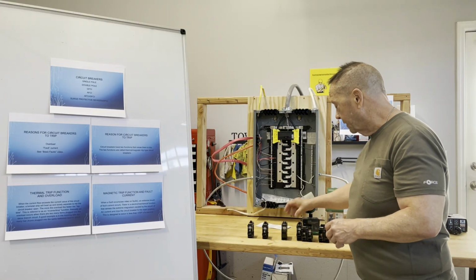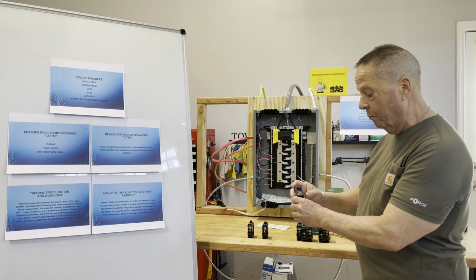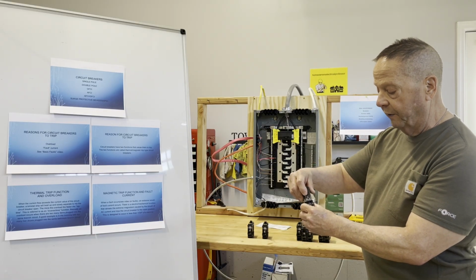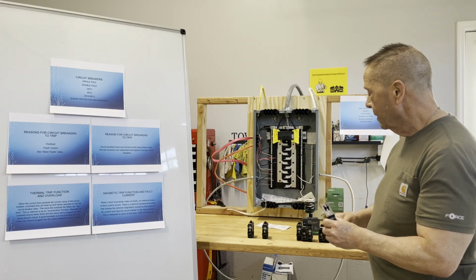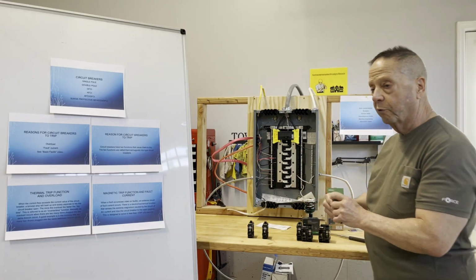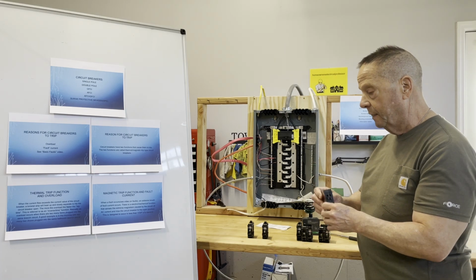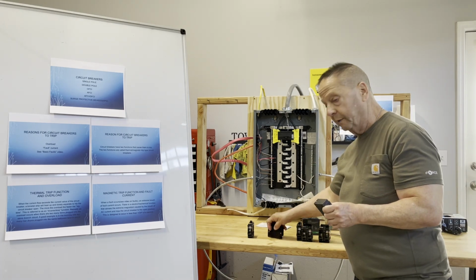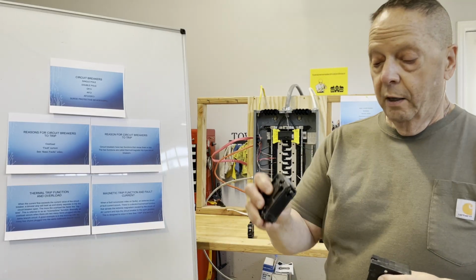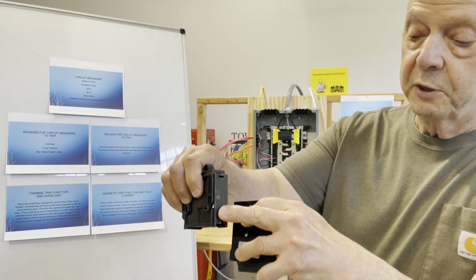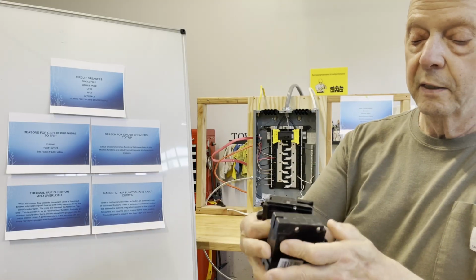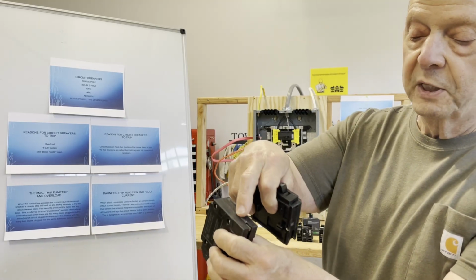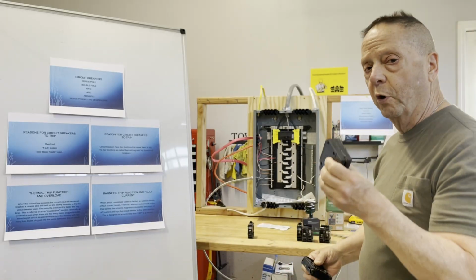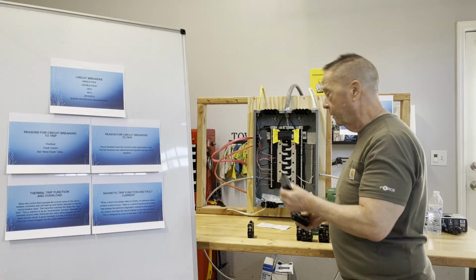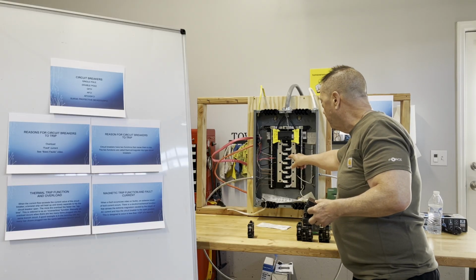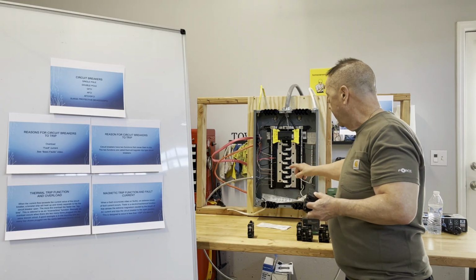The other thing I want to talk to you about is there are what are known as tandem breakers, where there are two breakers to fit on one spot, okay? If your panel starts to become crowded and you want to try to fit these in, there is one thing you have to be aware of, and that is that on a regular circuit breaker, if you see this space behind here, it's wide open. On a tandem circuit breaker, there's a tab here, and your panel will only accept a tandem circuit breaker if the bus bar stabs. I went over that on my main electrical panel.